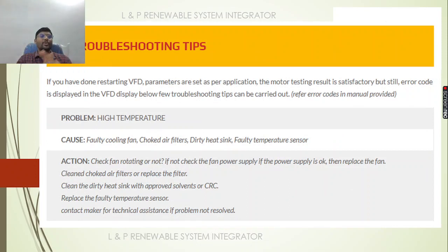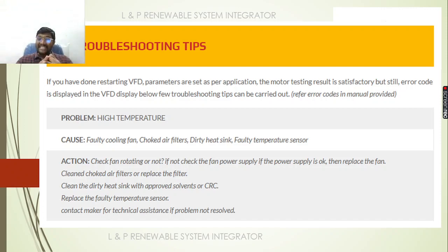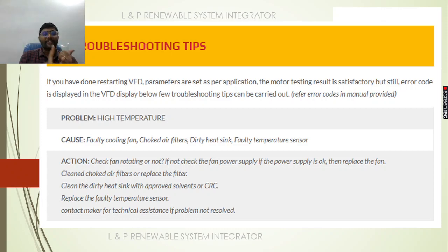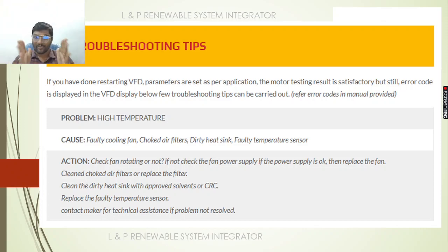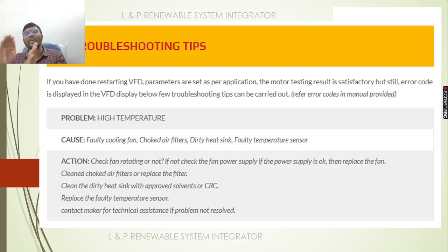Now we are going to see some troubleshooting tips. First and foremost, in the VFD, we often face a problem called high temperature. What will cause this high temperature? There is a possibility for a cooling fan to get faulty, choked air filters, dirty heat sinks, and faulty temperature sensors. The action we need to take: first, check whether the fan is rotating — if not, check the fan power supply; if the power supply is okay, replace the fan. Check whether the air filters are clean — if not, replace them. Check the heat sink and clean it with approved solvent. If there is any faulty temperature sensor, try to replace it. If the issue is not yet resolved after all these actions, it is better to contact the technical person.